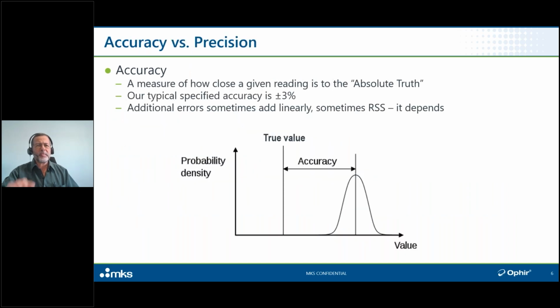We need to differentiate between two similar but not identical terms, accuracy and precision. Precision is sometimes also referred to as repeatability. The accuracy is what we just described. It's a measure of how close a given reading is to the absolute truth. Typical accuracy specification for our power sensors, let's say, might be plus minus 3%. For the very high power water-cooled sensors for multi-tens of kilowatt industrial beams, it might be a little higher, plus minus 5%, because there's a lot of additional noise from the water cooling and the mass of the sensor and so on. And then in the data sheets, by the way, there will also be a few additional things, additional error with frequency if it's an energy per pulse sensor, linearity with power, additional error with wavelength, all sorts of additional things. So wait a second, you might ask, does that mean that the actual bottom line uncertainty in my measurement is not plus minus 3%, but it'll be plus minus 3 plus 1 plus 2 plus 1%?